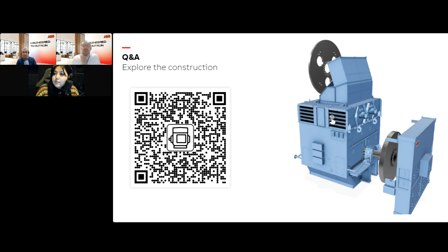Yeah, I can take that. That's related to the reliability of this generator as well. As mentioned, it has 4 cooling fans to circulate the cooling air and distribute it around the generator. But we have designed the system so that one of those cooling fans can be out of operation, and still with the 3 remaining fans you can have nominal output of this generator. So that has been considered within the design.